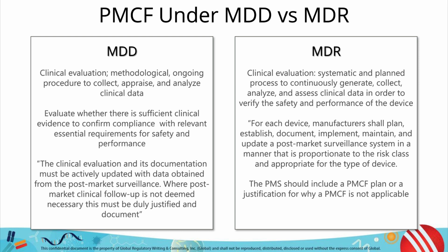Here we can take a look at the evolving requirements of PMCF from the MDD to the MDR. Under the MDR, manufacturers have to include a PMCF plan as part of their post-market surveillance process. If PMCF is not appropriate, this can be justified, but PMCF is a discrete and specific requirement.